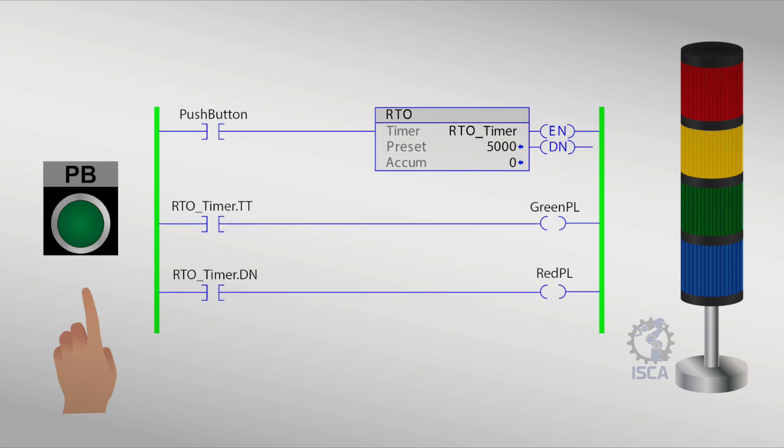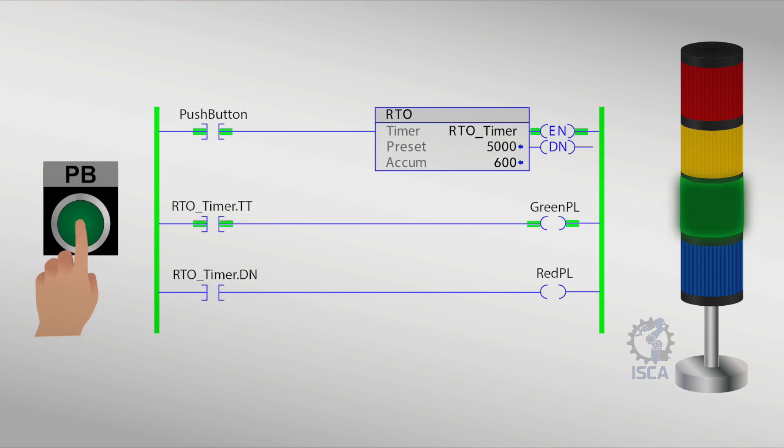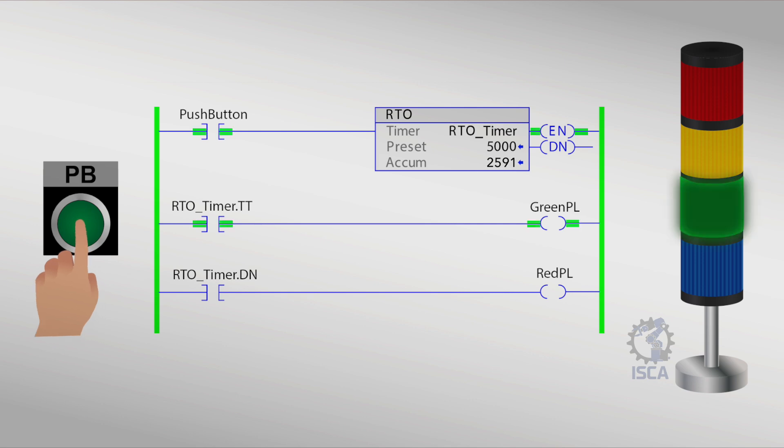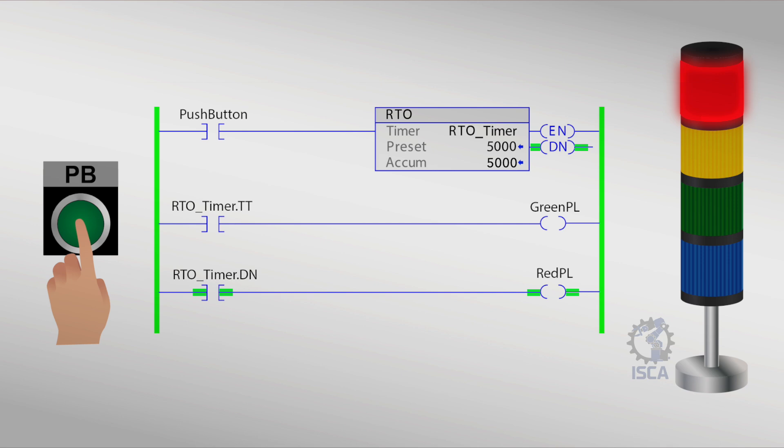The RTO or TONR timer used in structured text programming is like the TON instruction. With a difference, the RTO will retain its current value until it is energized again or forced to reset. It is an instruction that begins timing when the input turns on. If the input turns off, the elapsed time is retained. The timer resumes timing from the retained time value when the input turns on again. When the time reaches the set time, the timer stops timing and the done bit, DN, turns on.